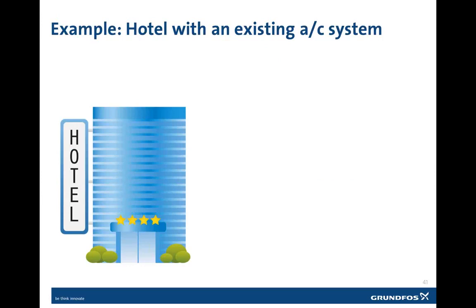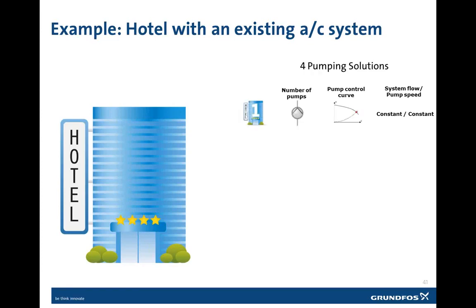Now words are one thing, so let's go through an example retrofitting of an existing hotel. What we're going to do is examine the life cycle cost, comparing a number of different pumps, control methodologies, and the pump flow and speed characteristics for the system. The first one we're going to look at is a single pump for this application running at constant speed, constant flow. The second consideration is, again, a single pump, but operating at constant speed using a variable flow control.